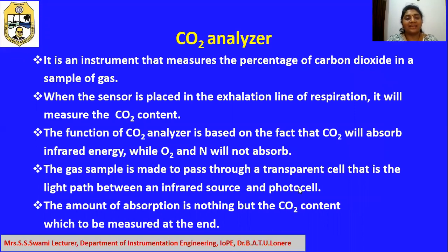So basically, a CO2 analyzer is an instrument that measures the percentage of carbon dioxide in a sample of gas. When the sensor is placed in the exhalation line of respiration, it will measure the CO2 content. The function of the CO2 analyzer is based on the fact that CO2 will absorb infrared energy while O2 and N will not absorb. The gas sample is made to pass through a transparent cell, that is, the light path between an infrared source and the photocell. The amount of absorption is nothing but the CO2 content, which is to be measured at the end.